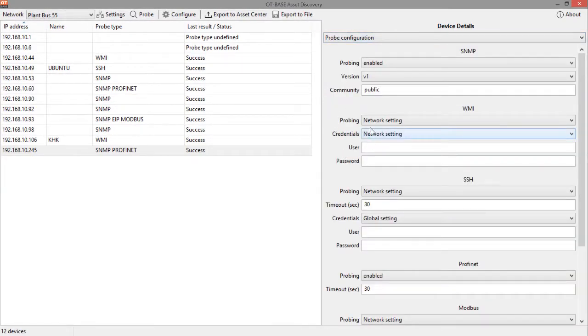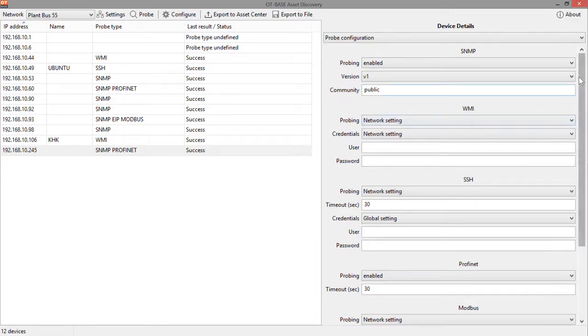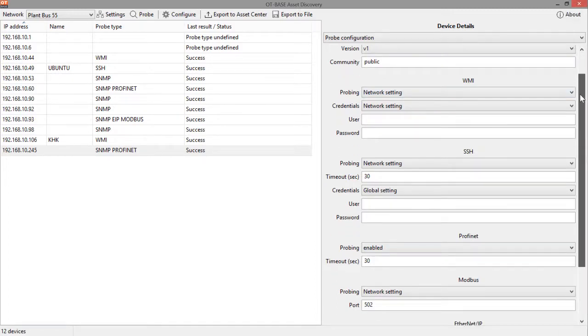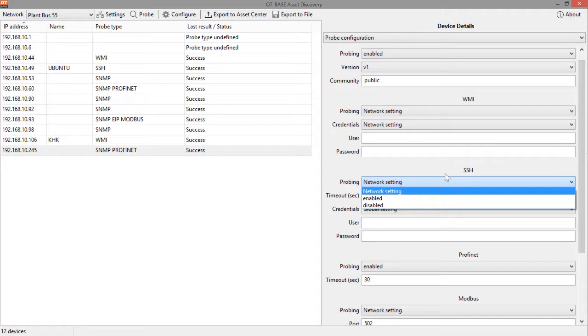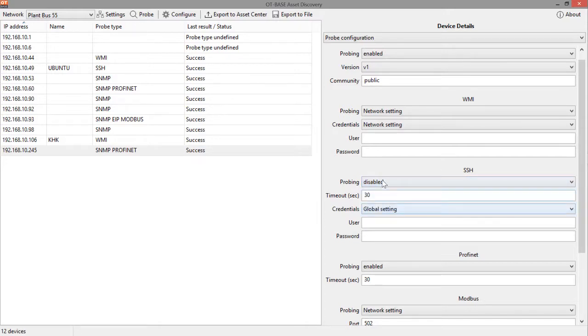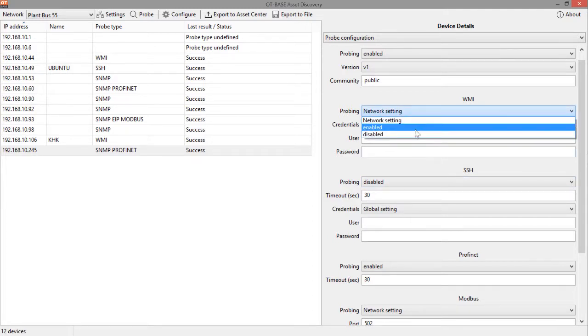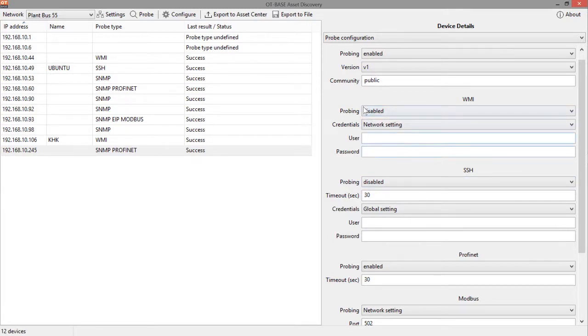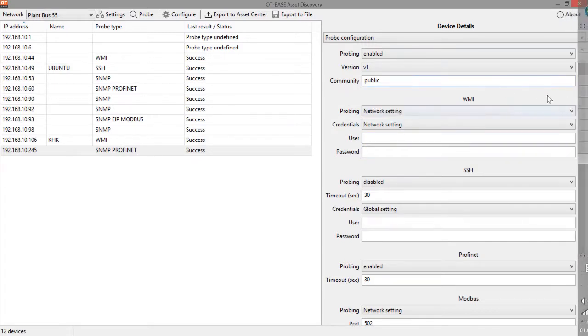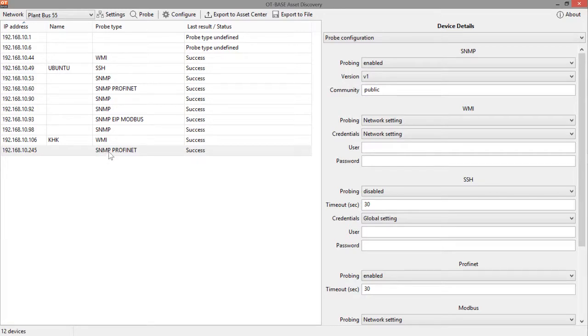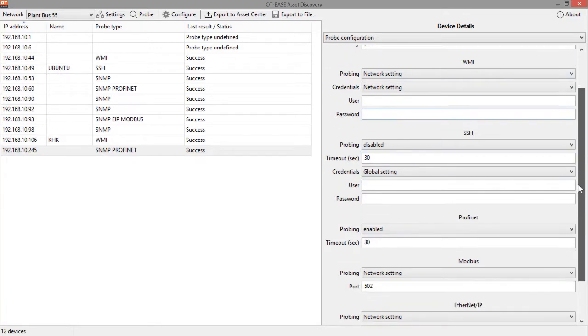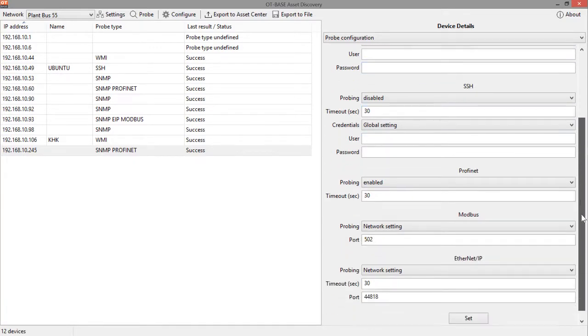Here we can see any connections, any data flow. And this is the area where we can fine tune the configuration, the probing configuration for this individual device. So as an example, we could specify we don't need any SSH probing for this device because we already know that it is an RTU which can be accessed by PROFINET. So we can simply disable SSH for this device. Same thing for WMI disabled.